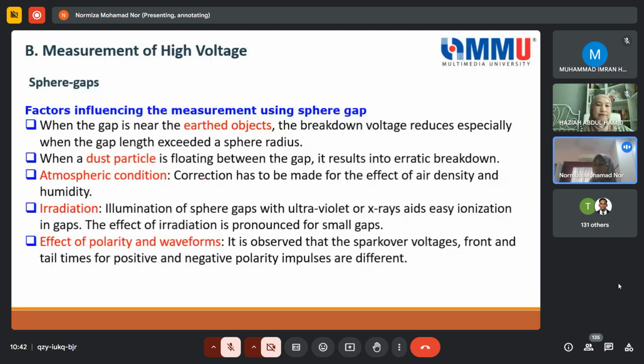So the factors influencing the measurement using sphere gap. One is the Earth object. When the gap is near the Earth object, the breakdown voltage reduces. So it means that when you have this spark gap and the distance from the ground is shorter, then the breakdown voltage that you expect, because you apply 150, of course you expect to have 150 kV here as well, but it may actually break down at lower voltage. It may occur at 130 kV. So this is very much influenced by the Earth object, not only from the ground but also from the surrounding.